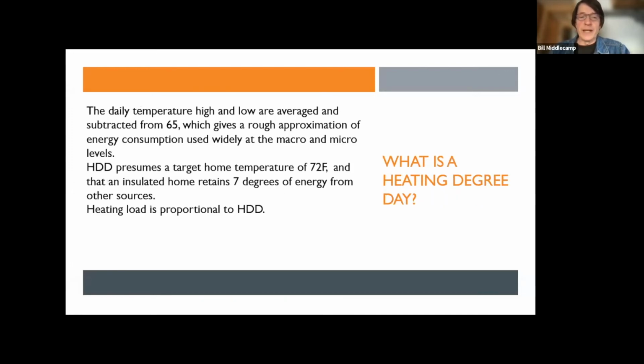So the heating degree day, once again, is a very simple calculation. They take the daily high and the low and they average them and then subtract that from 65. By the way, there's also a cooling degree day, which goes the other way. Temperature above 65 minus 65 gives you the number of cooling degree days. And as I said, the government and utility companies use the heating degree day as a rough approximation of how much energy is consumed in society, and they can plan for that. So it's used both at the macro level and the micro level.